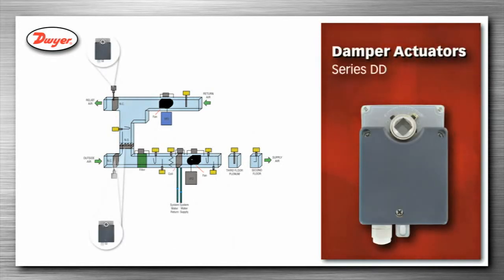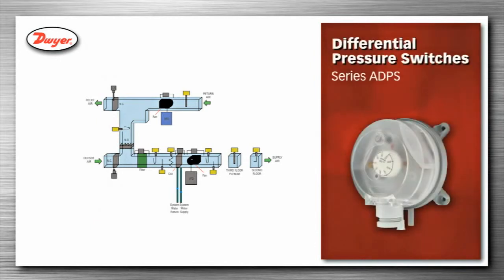Damper actuators, Series DD, are used to open and close dampers to change the airflow through the air handler. Differential pressure switches, Series ADPS, are used as a frozen coil alarm by monitoring the pressure loss across the coils in the duct to indicate a frozen coil condition. They are also used as a dirty filter alarm by monitoring the differential pressure loss across the filter.